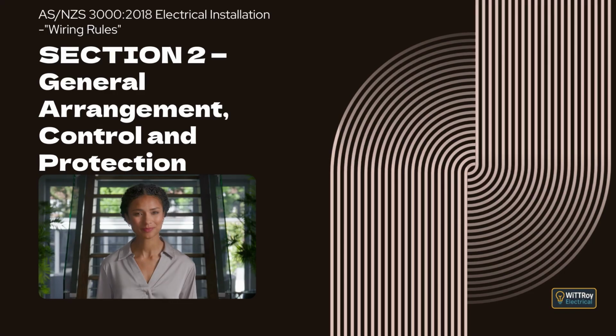Clause 2.4.2, Protection by automatic disconnection of supply. This clause explains the purpose of automatic disconnection. The idea is to limit the touch voltage during a fault. If a live conductor touches an exposed conductive part, the voltage on that metal must be removed quickly enough to prevent electric shock. To achieve this, two things must happen.